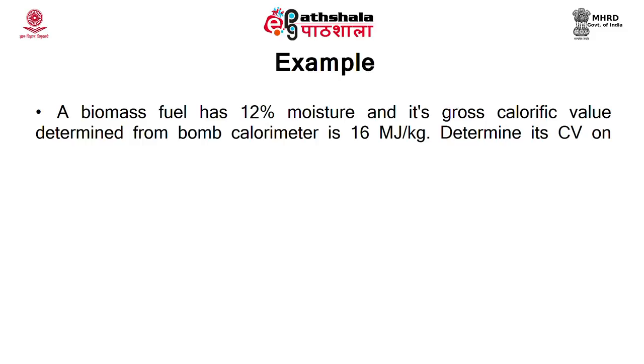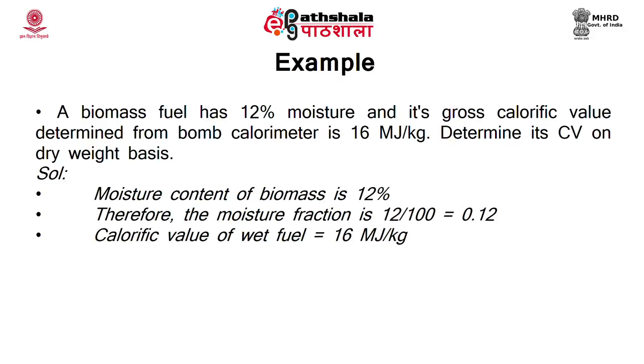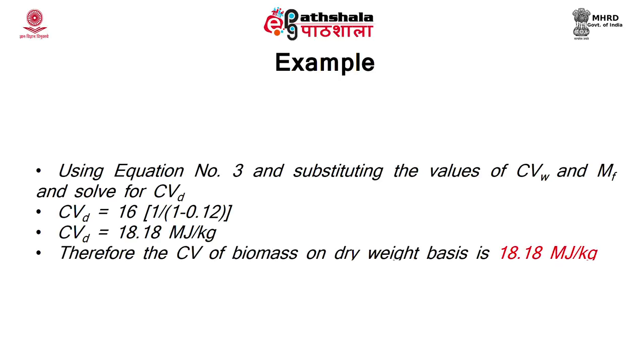Example: A biomass fuel has 12% moisture and its gross calorific value from the bomb calorimeter is 16 MJ/kg. Determine the calorific value on dry weight basis. Moisture fraction Mf = 12/100 = 0.12. CVw = 16 MJ/kg. Using CVd = CVw × 1/(1 − Mf): CVd = 16 × 1/(1 − 0.12) = 18.18 MJ/kg. Therefore, the calorific value of biomass on dry weight basis is 18.18 MJ/kg.